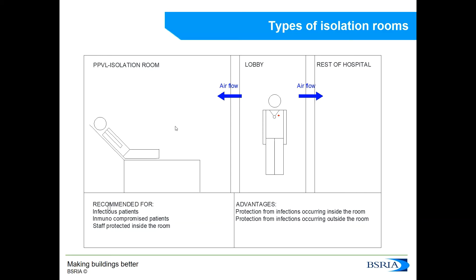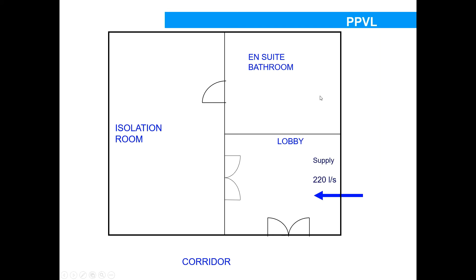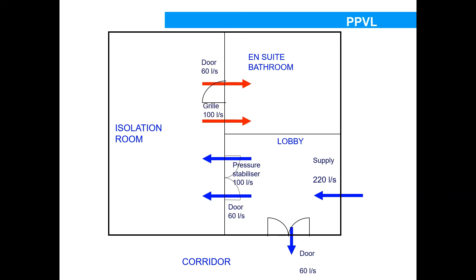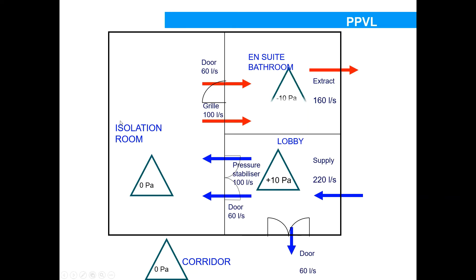These rooms can be used for both immunocompromised and infectious patients. One of the designs that BSRIA has tested and validated — and the design we are looking at for air tightness tests today — consists of an entrance, a positively pressurized ventilated lobby, the patient's room or isolation room, and the en suite bathroom. Air is supplied mechanically into the lobby; the lobby gets pressurized. Some air goes through gaps in the door into the hospital or into the patient's room. Most air goes through the pressure stabilizer above the door — approximately 100 litres per second — into the isolation room, where it mixes, dilutes contaminants, and is then extracted through the en suite bathroom, filtered, and expelled outside.